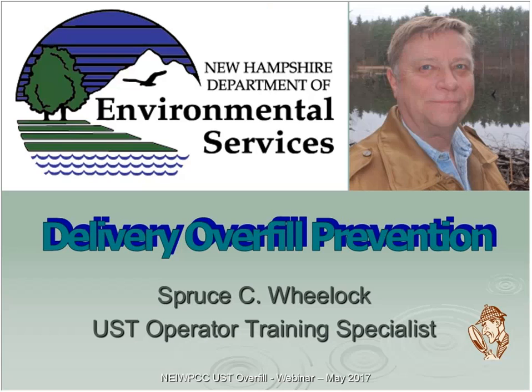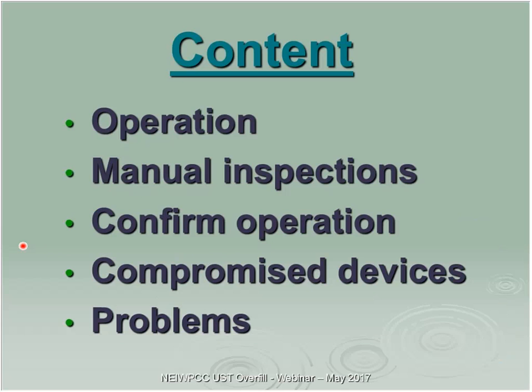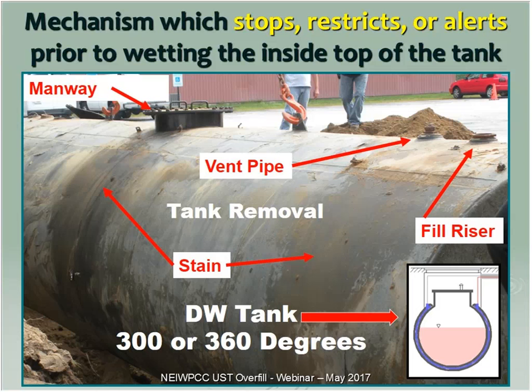First off, it's a mechanism which stops, restricts, or alerts prior to wetting the inside of the tank. In New Hampshire, all our tanks are now double-walled. In the early days there were only 300-degree wraps, so the very top section was not double-walled. Currently with all new tanks there are 360-degree wraps — but if you look at a removed tank, most of our contamination is where the fittings are, because that's still single-wall and that's where we're getting most of our contamination these days.